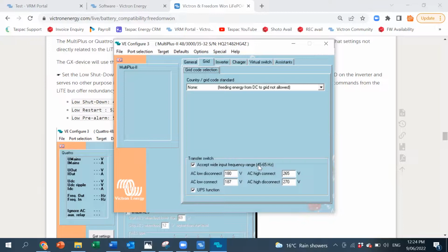Accept a wide range of frequency, that's good. And also low voltage and high voltage, you want that as wide as possible to accept whatever the generator throws at it. UPS function basically matches the inverter really close to the generator waveform, and as soon as the generator starts wavering or shutting down, looking like it's going to shut down, the inverter drops it off and takes over. So if you've got a dodgy generator, it's best to untick the UPS function. That means they might get a couple of flickering lights as the generator disconnects. But if you have a UPS function on there, it's going to kick out any dirty generator, and some generators won't even connect.